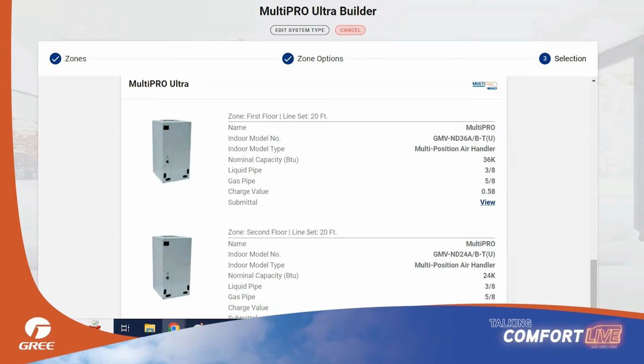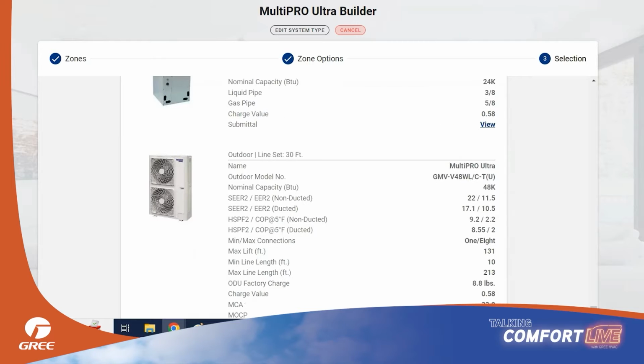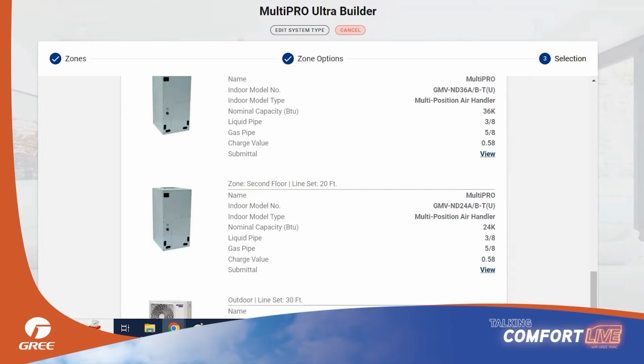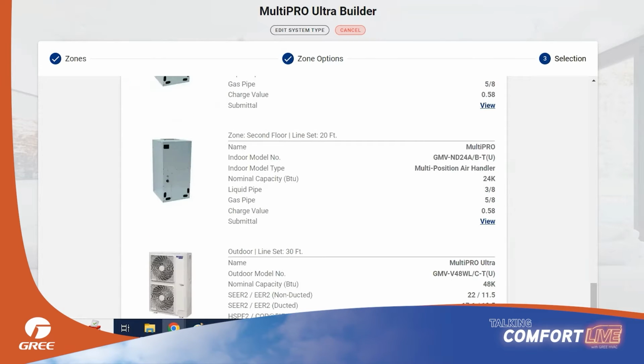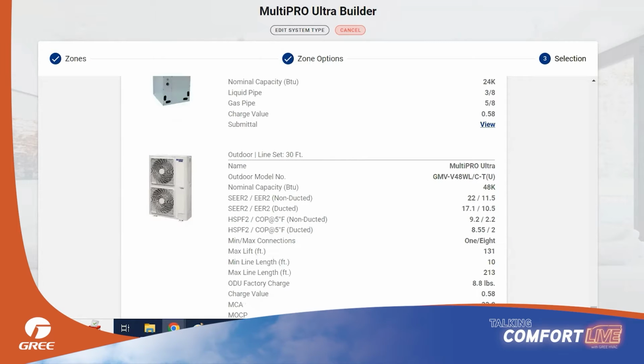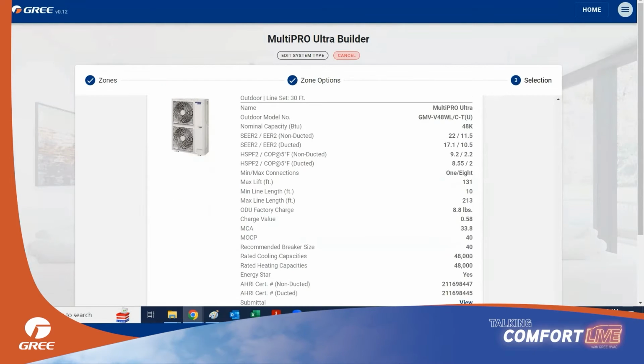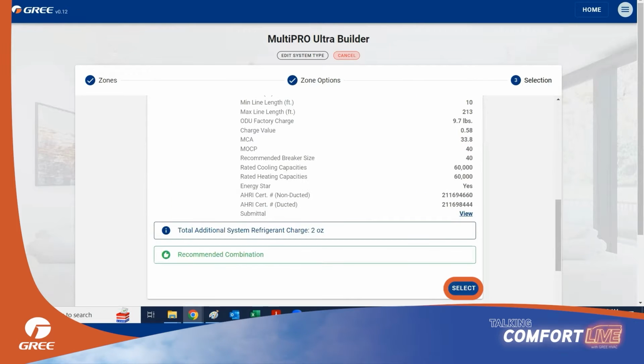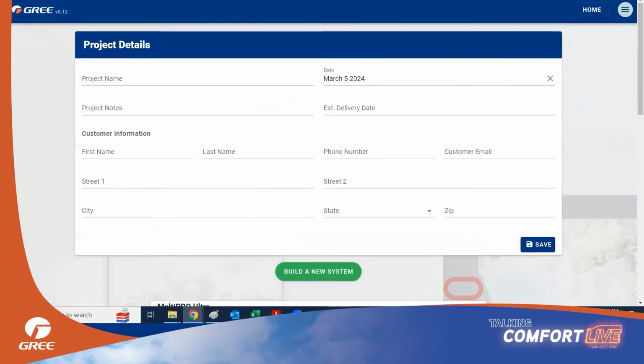All right, next, the system down here. This is not the recommended combination, but this is a combination that absolutely can work. You've got a 3-ton air handler and a 2-ton air handler, and then a 4-ton outdoor unit. So where this mostly comes in handy is when you've got multiple zones, and each of those zones is slightly oversized, and so your total connected capacity of indoor units exceeds the total required capacity. So you can get away with using a smaller outdoor unit. Okay. So we're going to select this system up here with the 5-ton.